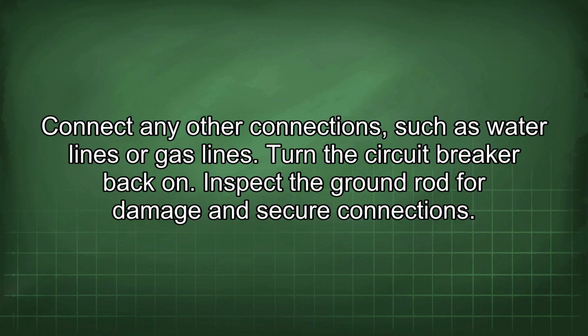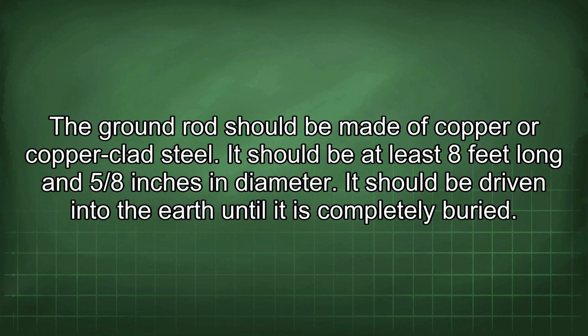Inspect the ground rod for damage and secure connections. The ground rod should be made of copper or copper-clad steel. It should be at least 8 feet long and 5/8 inches in diameter. It should be driven into the earth until it is completely buried.